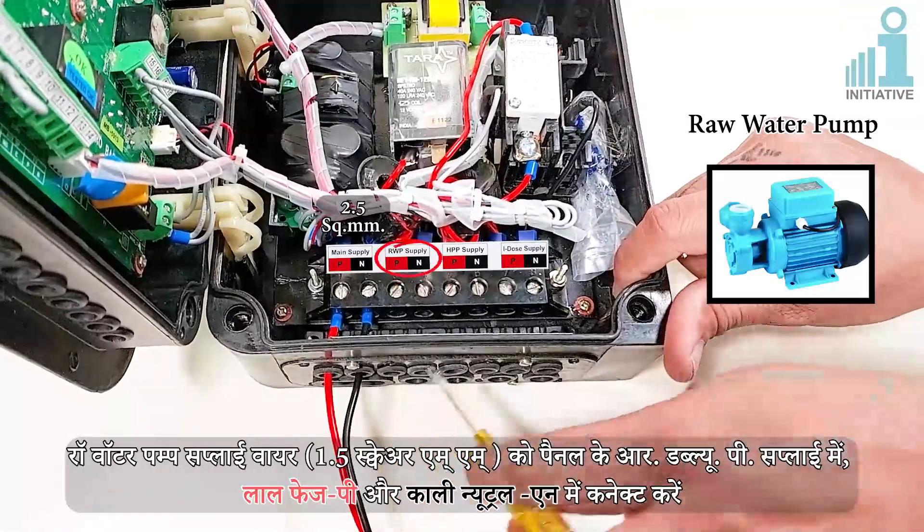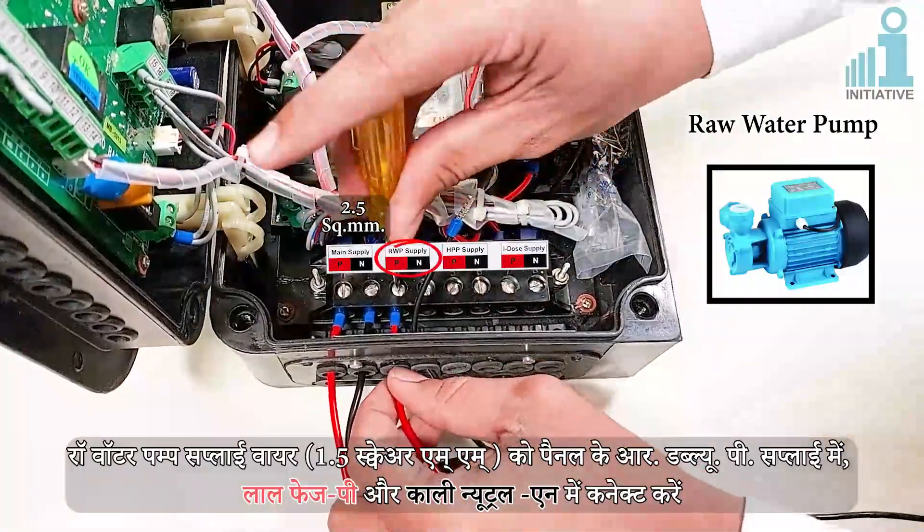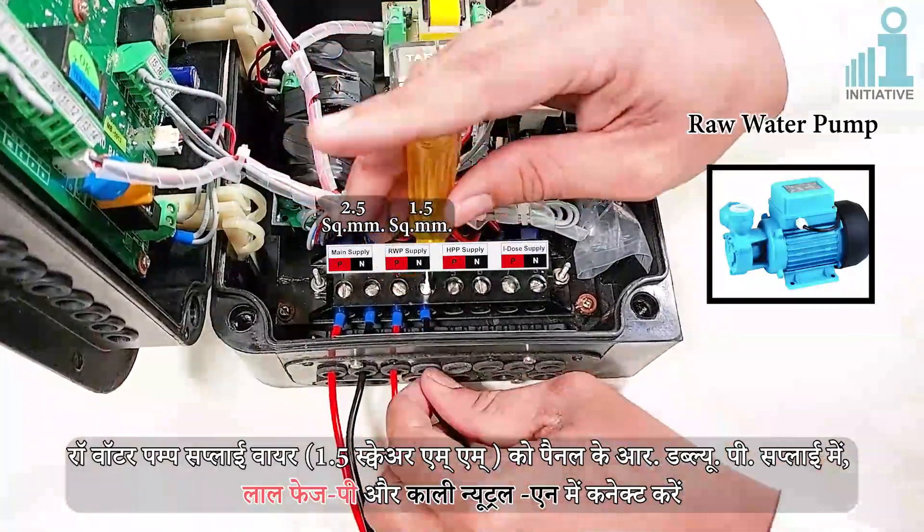Connect the raw water pump supply cable of 1.5 sq. mm to the panel's RWP supply connectors: red for Phase (P) and black for Neutral (N).